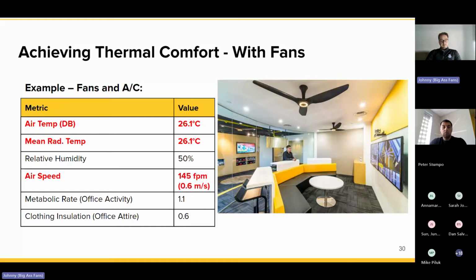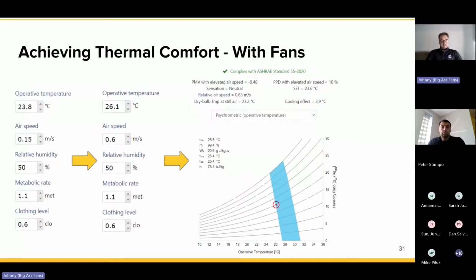But what we're adding here is a modest air speed of 145 feet per minute. So this would be comfortable for an office. This is not going to be disruptive, but it's going to get you a little bit of a cooling effect to supplement that ultimate cooling load that we're sacrificing by raising the set point. So what does this look like when we plot it? Again, people are still comfortable. PMV stayed relatively flat, negative 0.48, and we still have 90% of people satisfied in the space. So we've raised the set point almost 3 degrees. We're saving, again, between 3 to 6% per degree, and the sensation is neutral.